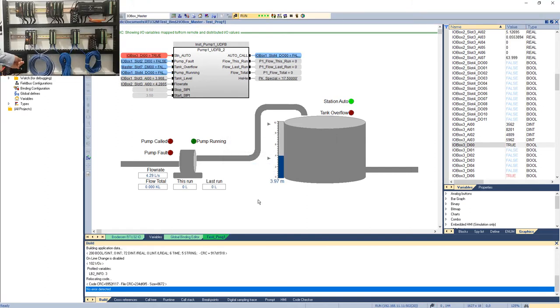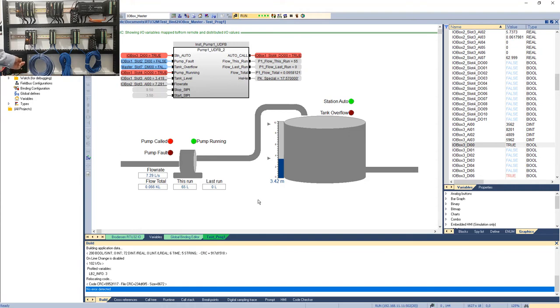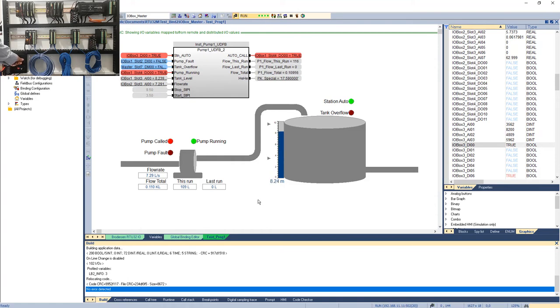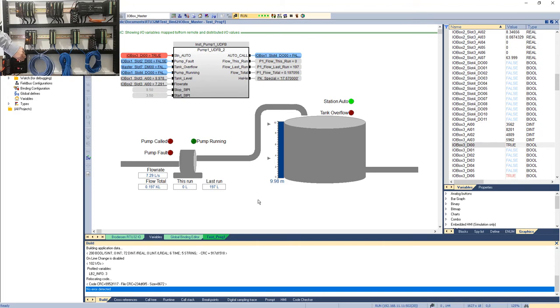Let's get online with this RTU. So we'll drop below 3.5, we'll get our tank to run. If I lean over here and I move to station 2, I can wind up some flow rate. That'll make our tank fill faster. Up we go. So expectation is we get to that top point where we're exceeding 9.5, we're asking our pump to stop running. Come back down again. We'll just prove again that it works.